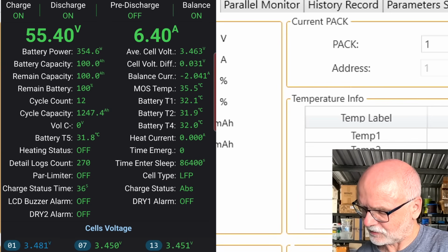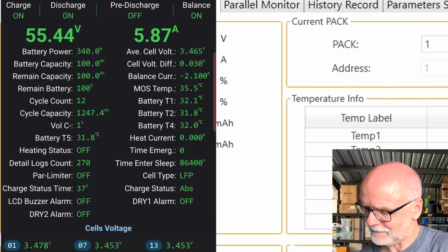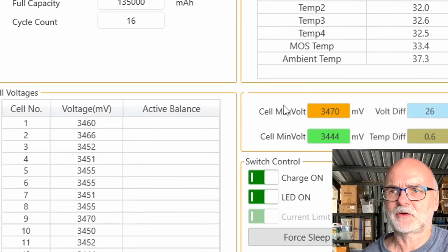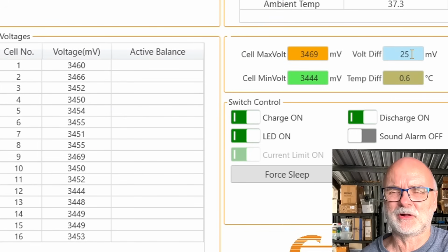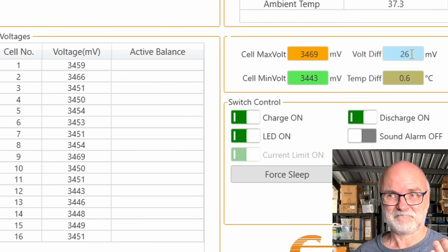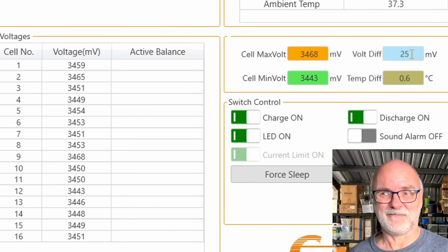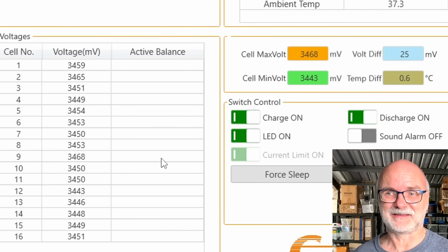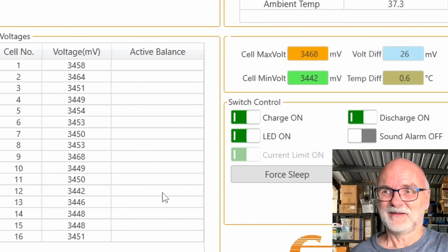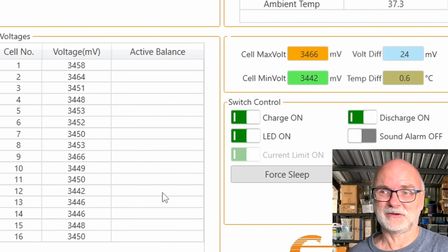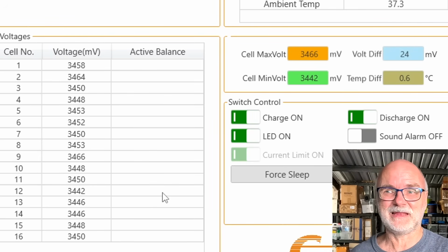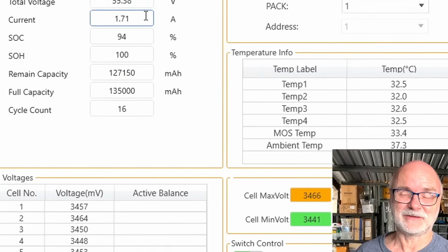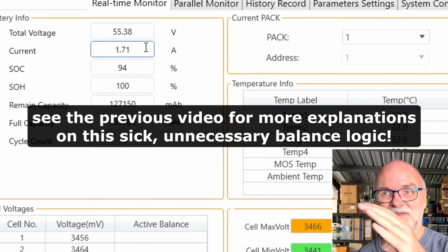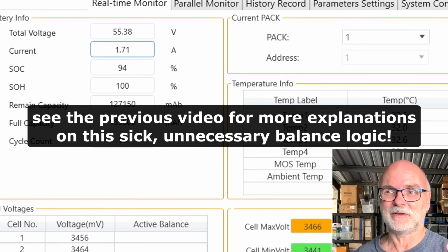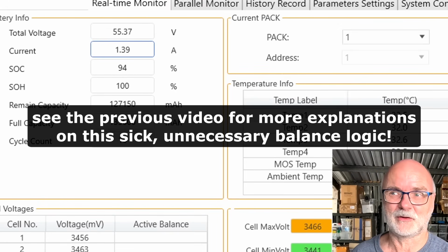The balancer has kicked in. We've got a deviation of 30 millivolts, and here 26 millivolts, which is under 50 millivolts, so the balancer doesn't start. It needs a trigger differential voltage across all cells of 50 millivolts. If the current is still above 2 amps - it's now just under 2 amps - so now it needs 30 millivolts of deviation, otherwise the balancer will not even start.